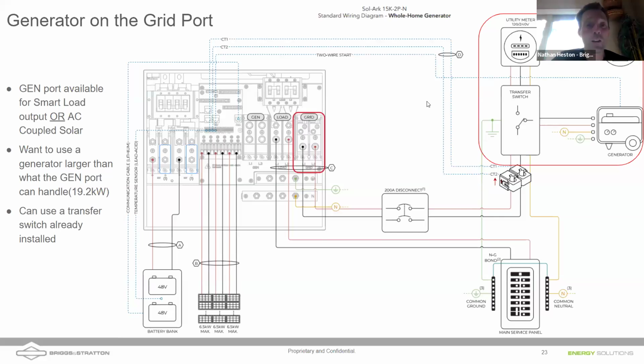You pointed that out very well, and maybe you're getting to this, but we've got solar on this system. Well, what if this system is programmed to send power back to the grid? Well, we don't want to run a generator backwards, is what you're hinting at, Nathan. And that, I think, speaks well to the capabilities of the Sol-Ark. So I've heard John Cromer, one of the head trainers at Sol-Ark, explain it like this: when we have that solar, and perhaps it's a sunny day, and whatever the reason, the generator is still running, we're backfeeding the grid, right? That's what we want to do in a normal grid-up situation.